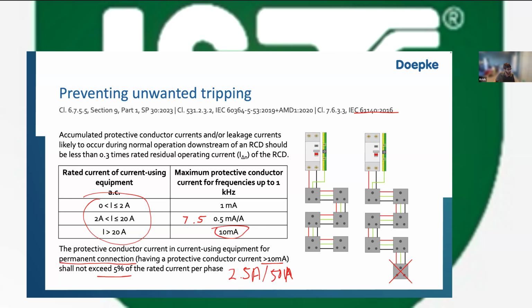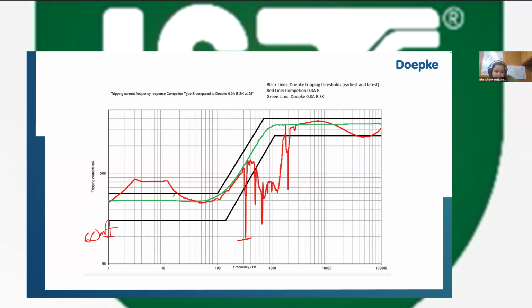A practical issue on site is the nuisance tripping of RCCBs. Does using a Type B RCCB help with this? I'd say particularly for elevator applications this is very important, because if you use the wrong type of RCD, or a Type B that is not tuned to the correct frequencies, as I showed in this graph, a 300 milliampere RCD can trip with 60 milliamperes of leakage current. So absolutely, using the correct Type B that is tuned for the frequency that you require, in this case up to 150 kilohertz, is more than enough. It will prevent nuisance tripping in this case. So yes, to answer your question.